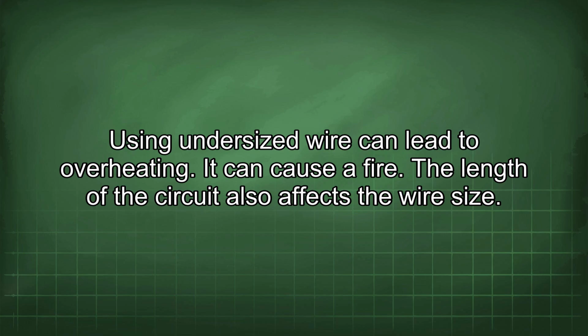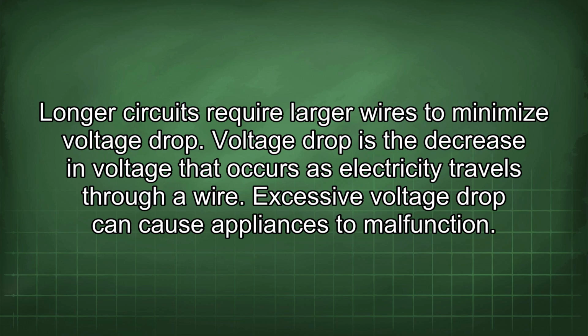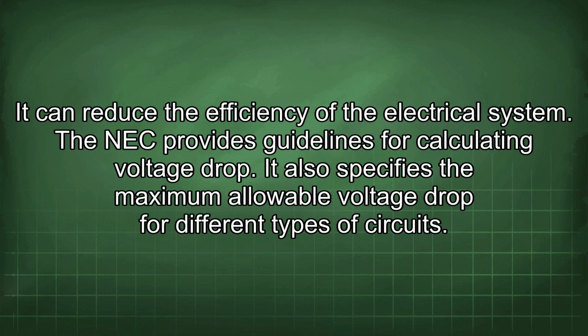The length of the circuit also affects the wire size. Longer circuits require larger wires to minimize voltage drop. Voltage drop is the decrease in voltage that occurs as electricity travels through a wire. Excessive voltage drop can cause appliances to malfunction. It can reduce the efficiency of the electrical system. The NEC provides guidelines for calculating voltage drop. It also specifies the maximum allowable voltage drop for different types of circuits.